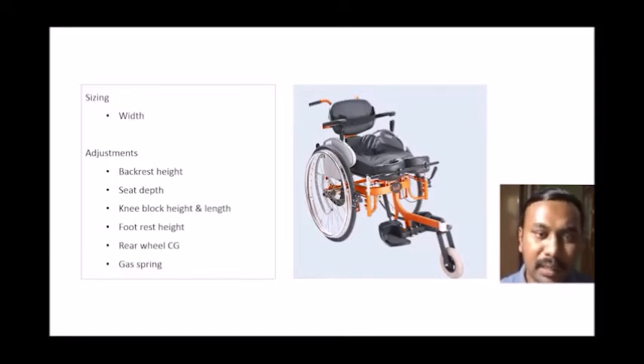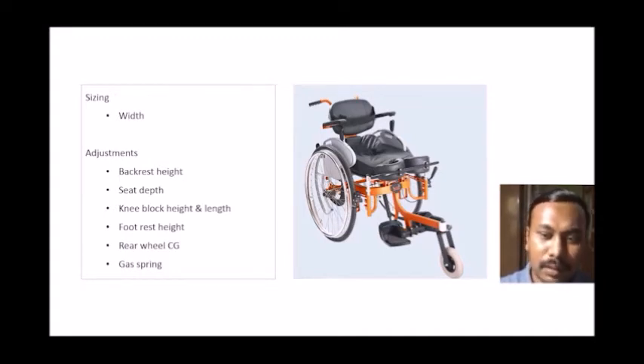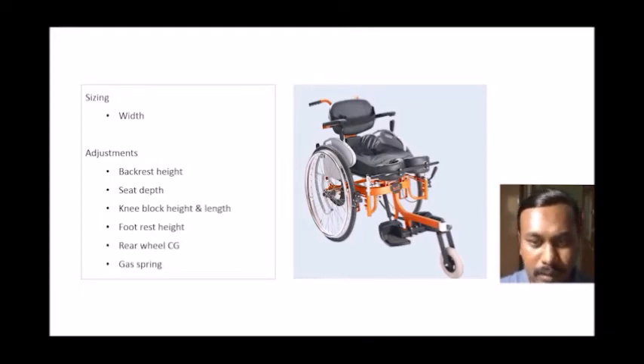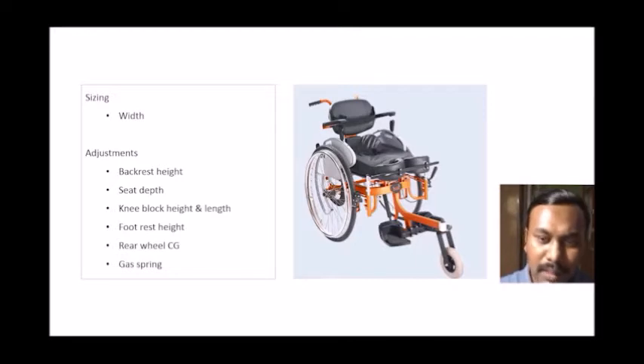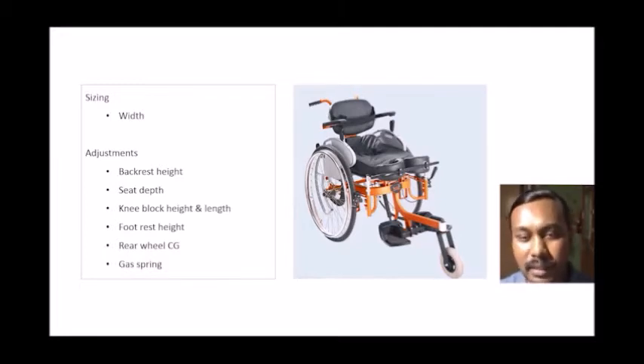We saw about sizes and adjustments: there are four different widths of the wheelchair — 15 to 19 inches — and multiple adjustments available. We can adjust the backrest height, seat depth, knee block length and height, footrest height, center of gravity, and gas spring. However, seat width alone is not adjustable — we have different sizes, so the first priority is finding the exact size that fits the person.